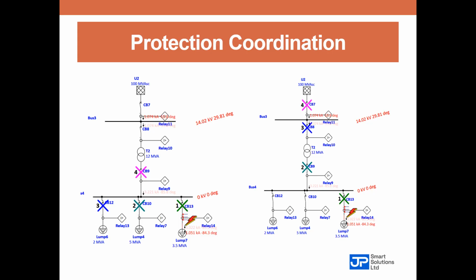Okay, now when we say protection coordination, let me explain it using this system. Protection coordination is all about backup protection. So if a particular breaker fails to operate or a particular relay fails to operate, the next relay or circuit breaker should operate to isolate that fault. So in this case, we have these two systems. So we have the fault at this location. Now let's assume on both cases, circuit breaker 13 is the first to open, which is the right operation. It is the correct operation. It is the first to open based on the location of this fault.